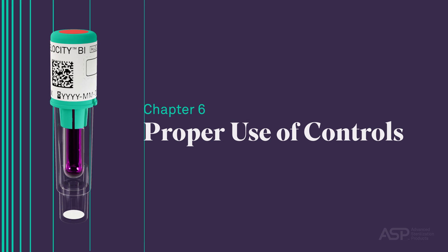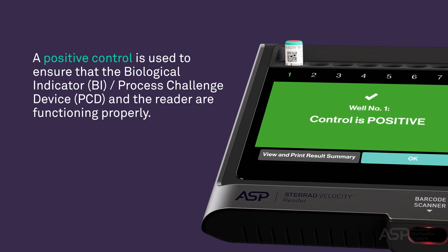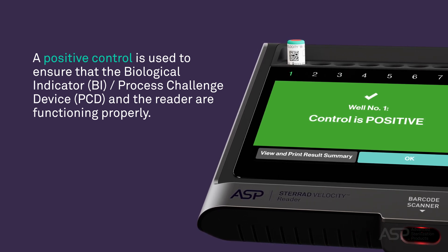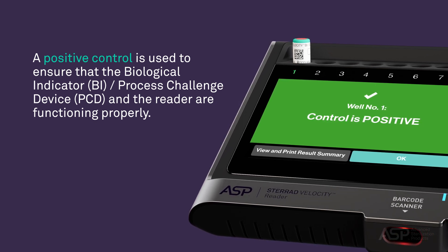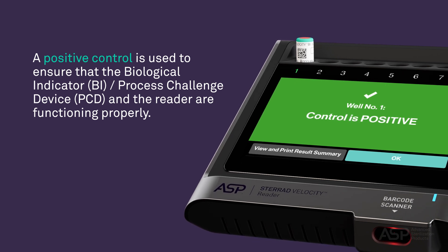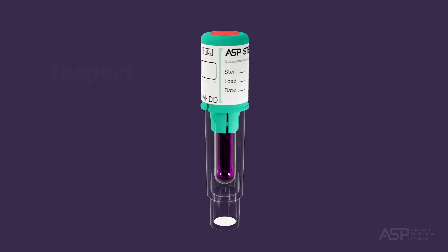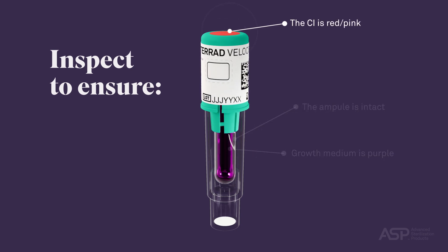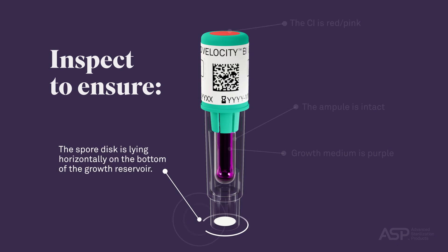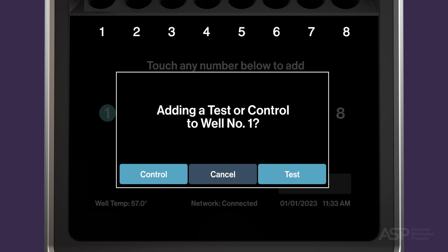Proper Use of Controls. A positive control is used to ensure that the Biological Indicator Process Challenge Device and the reader are functioning properly. A positive control is an unprocessed STERRAD Velocity BI PCD which is activated and read in the STERRAD Velocity Reader. To perform this control, select a positive control BI PCD from the same lot as the test BI PCD. Inspect it to ensure the growth medium is purple, the ampule is intact, the chemical indicator on the cap is red-pink, and the spore disc is lying horizontally in the bottom of the growth reservoir. Then touch an available well indicator number on the reader's touch screen.